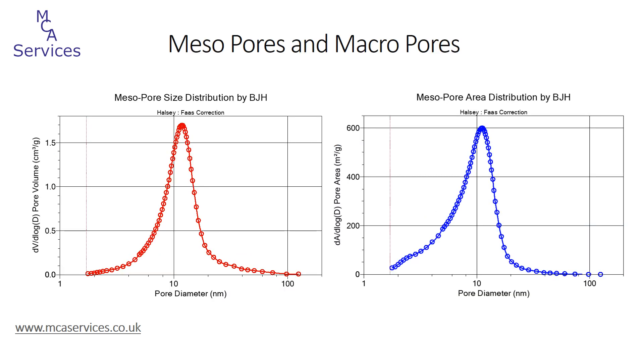Moving to the higher relative pressure end of the isotherm, we can obtain mesopore size, volume, and area information, and this can also be extended into the macropore range, but this particular sample has a well-ordered, distinctly mesoporous pore structure. We've applied the BJH model — named after its creators Barrett, Joyner and Halenda — to the adsorption isotherm. The plot on the left shows the pore size distribution according to pore volume: the sample is distinctly mesoporous, with pores in the range of 3 to 35 nanometres diameter and the peak maximum occurring at 12 nanometres. The plot on the right shows the pore area distribution. The plots look quite similar, but the pore area plot does show a greater skew towards smaller pores, which is reasonable since for a given pore volume, smaller pores will contribute more to total pore area than larger pores.